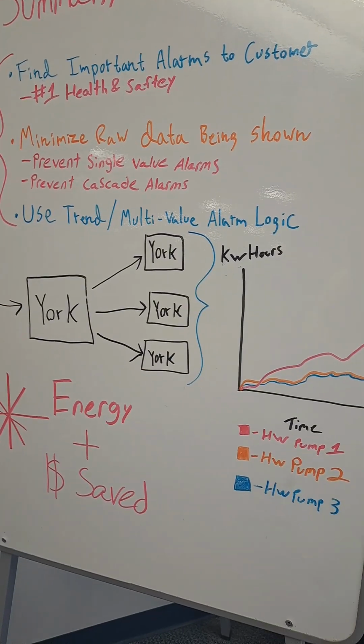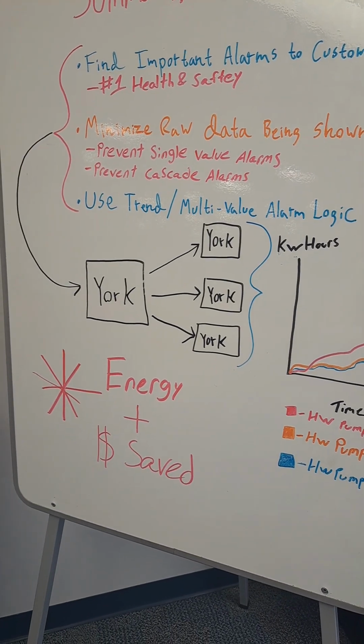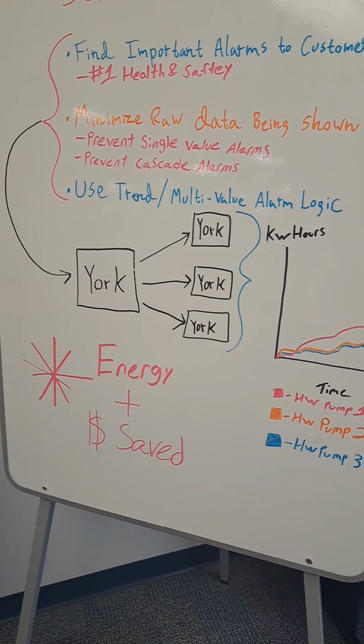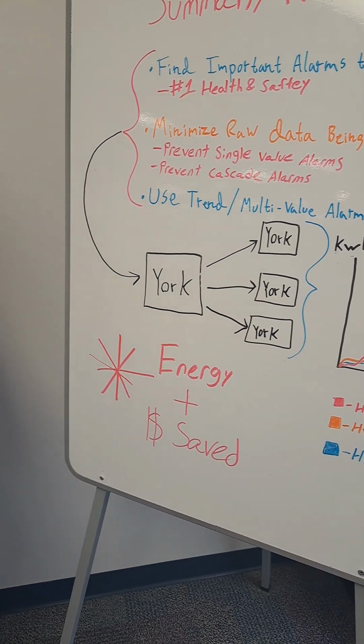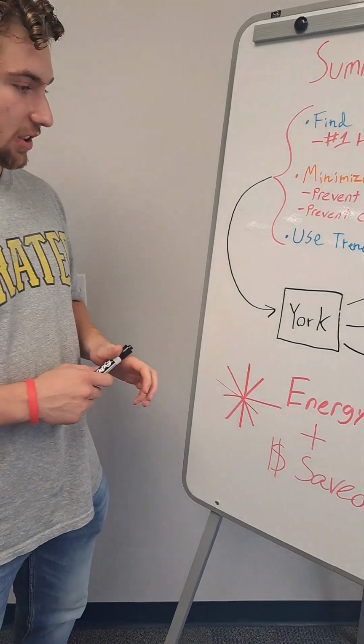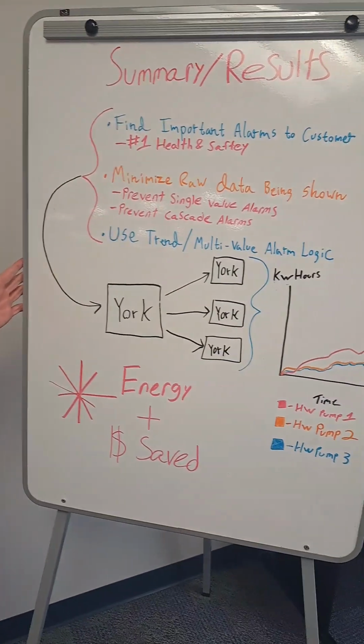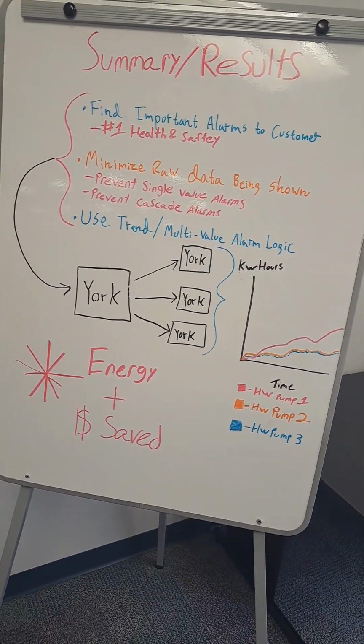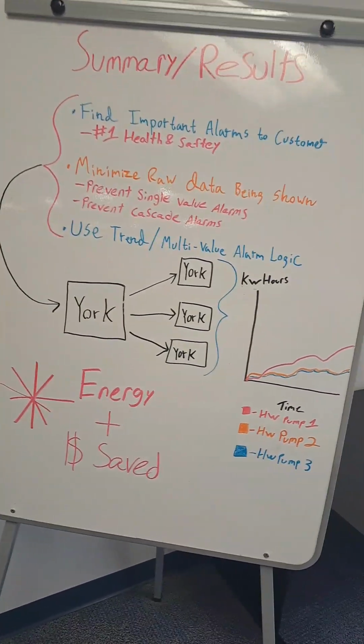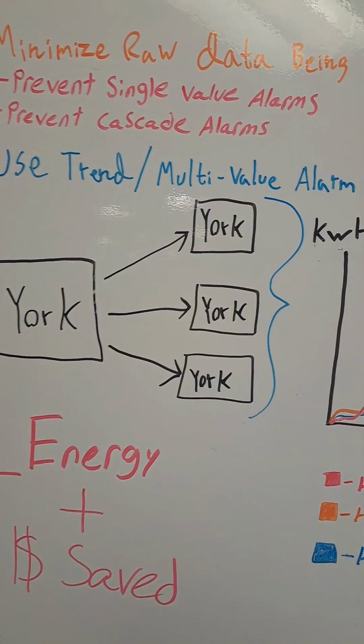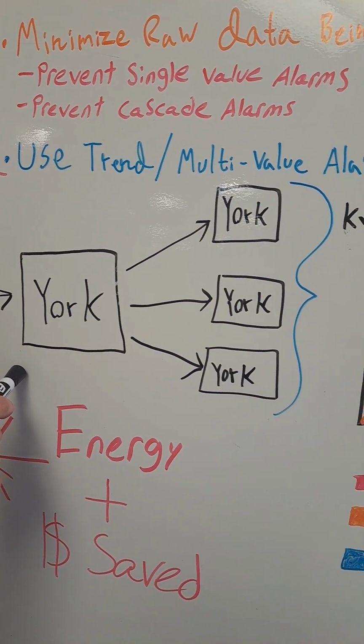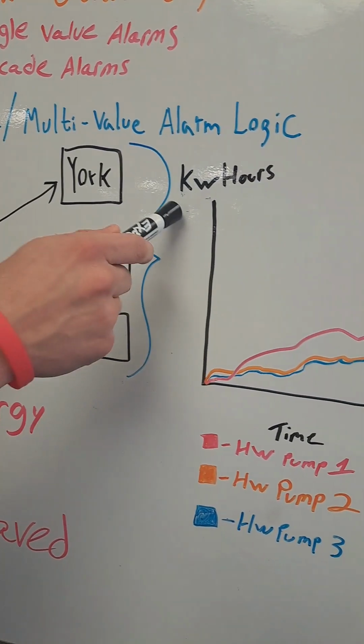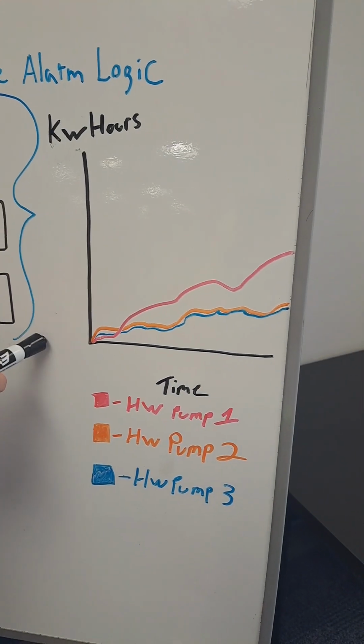And it also saves them on their energy bill. And the third thing is use trend values for alarms. This can show what is going on with the system, where the issue might be. For this example, there's 3 York pumps. They're all communicating through a BMS system, and we have a trend line set up with kilowatt hours and time.